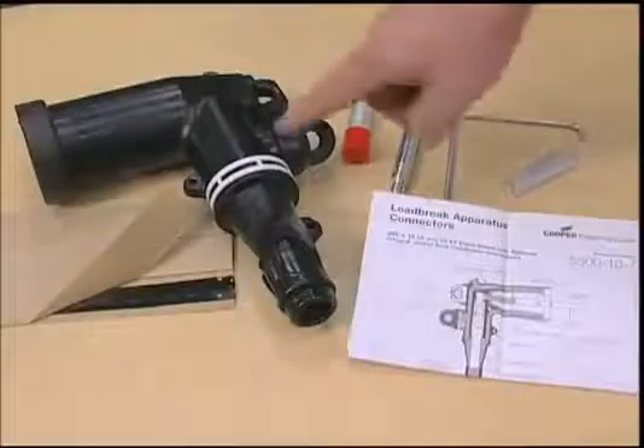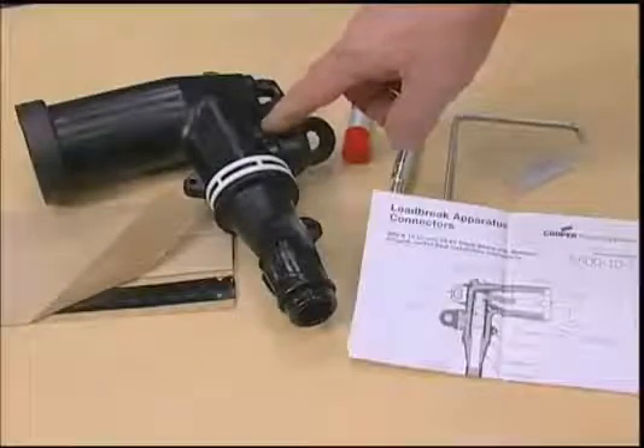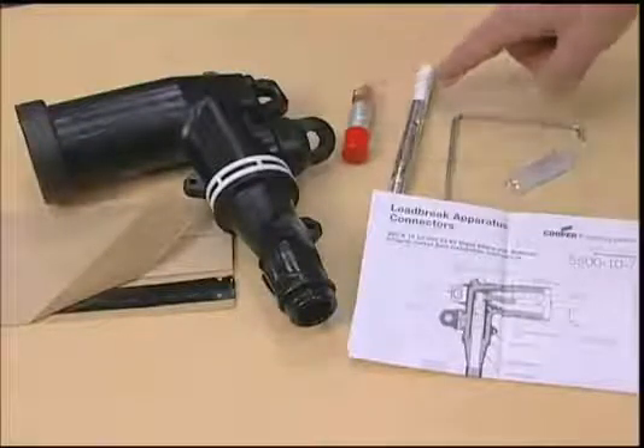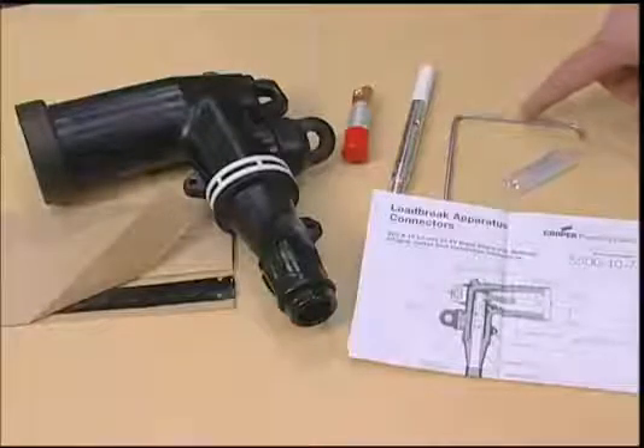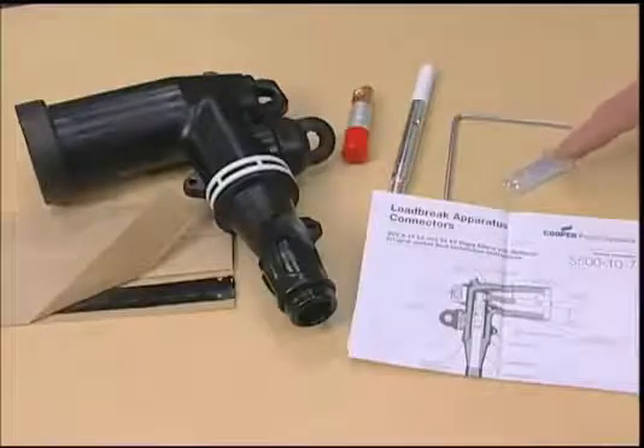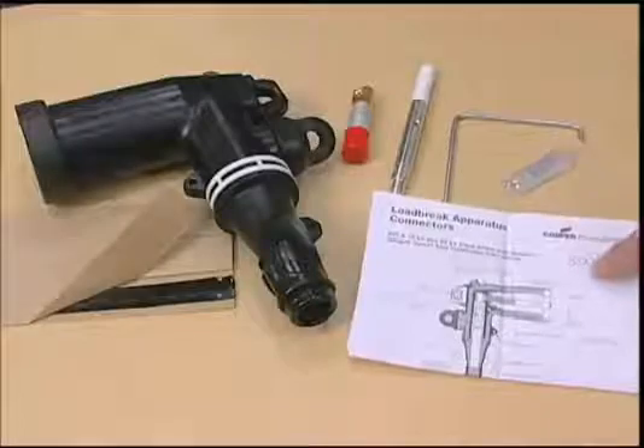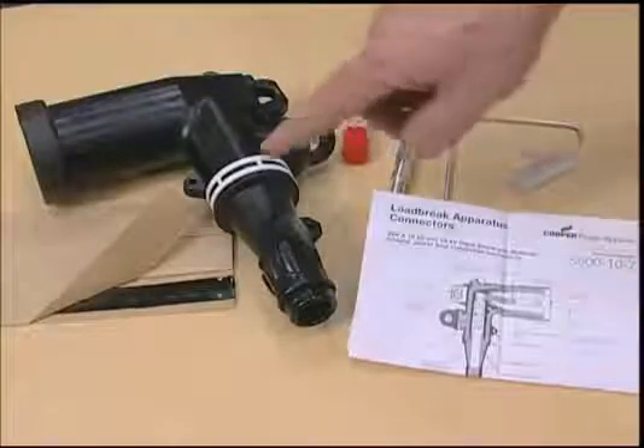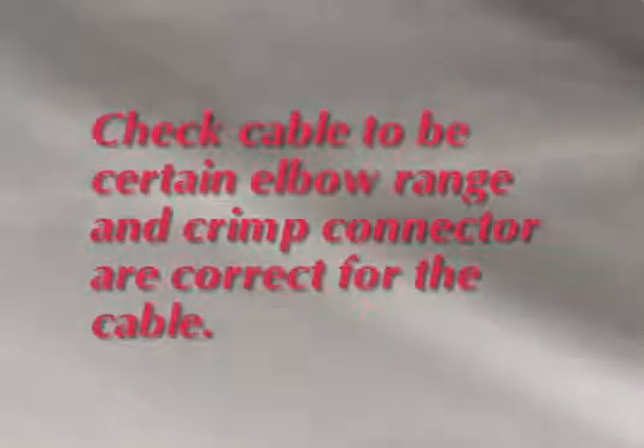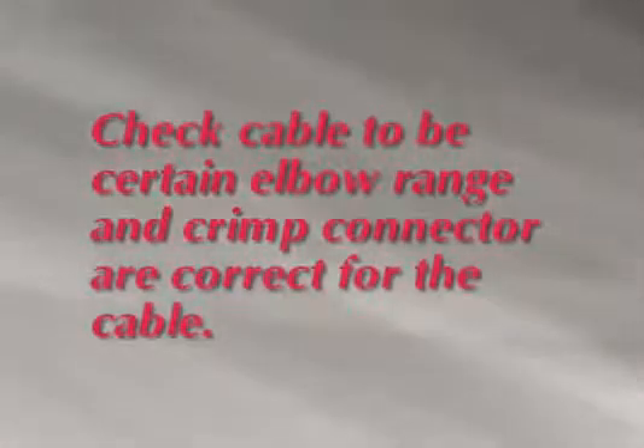The elbow kit includes the elbow with integral jacket seal, copper top crimp connector, probe, wrench, silicone grease, and installation instructions. Also included, mastic tape for the integral jacket seal. Check the cable to be certain the elbow range and crimp connector are correct for the cable.